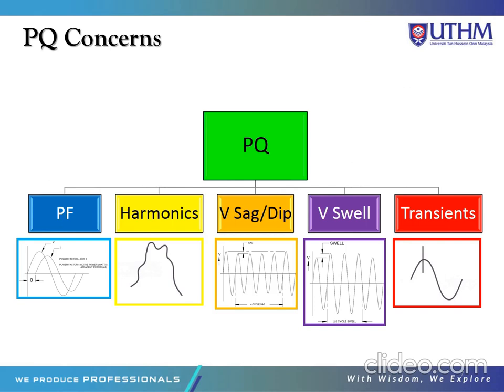Here are the PQ concerns. There are some parameters involved in PQ. The first one is power factor. The second one is harmonics, which is some disturbance occurring in the curve. Then we have voltage sag or dip, where we can see a drop in voltage value from the actual. Then we have voltage swell, where there is an increase in the voltage value. And lastly is transient, which is a disturbance or higher value for a certain period.